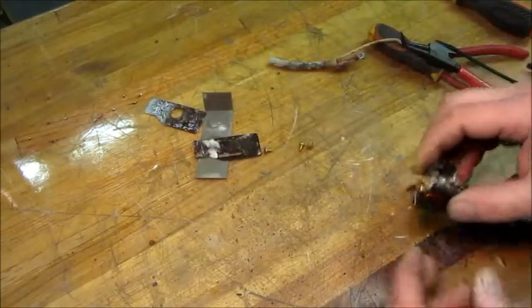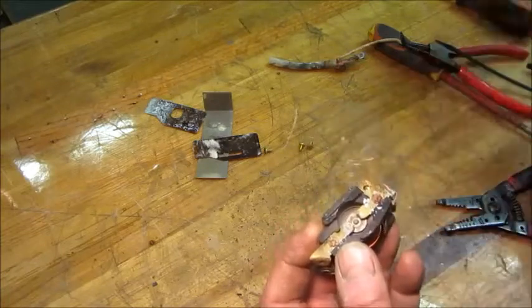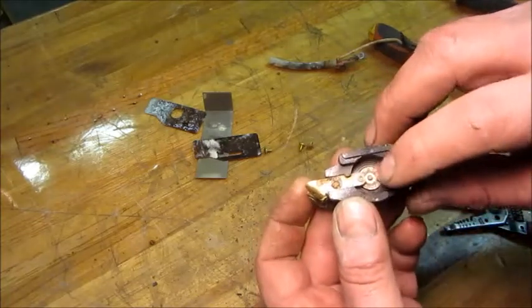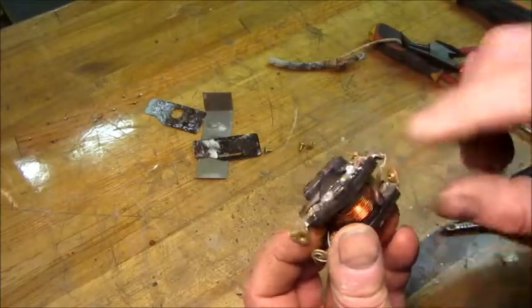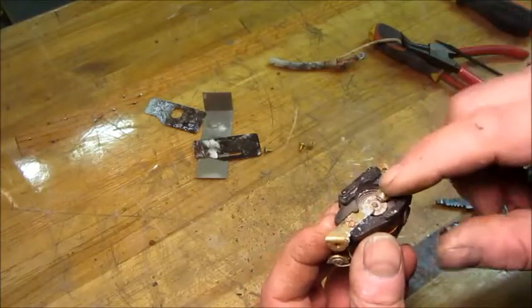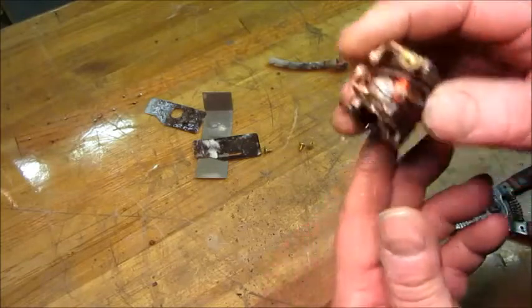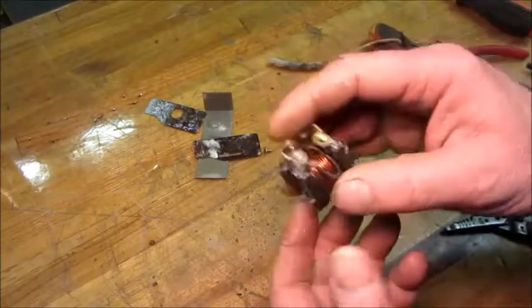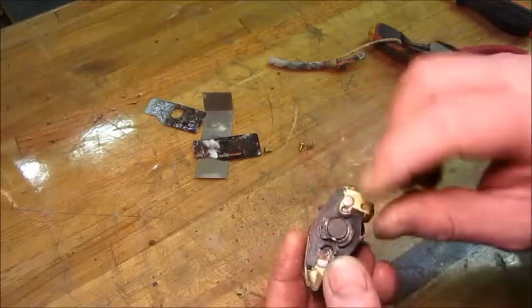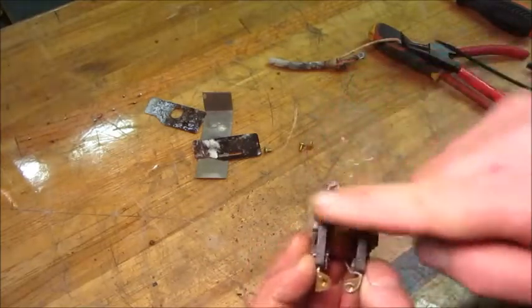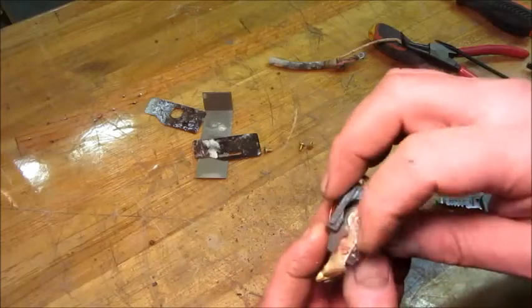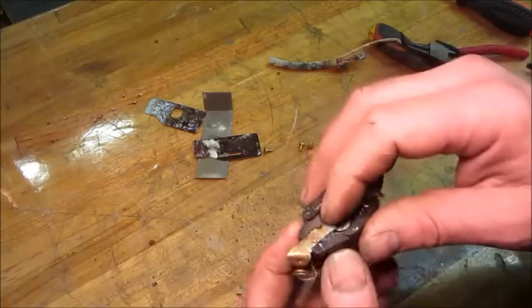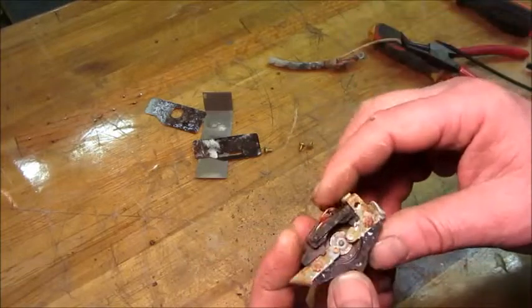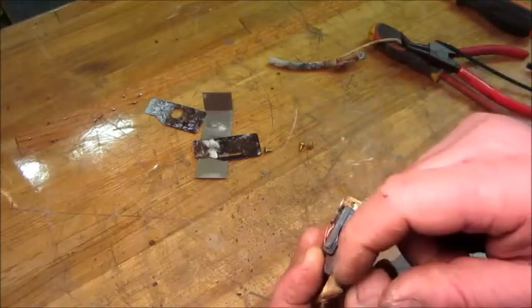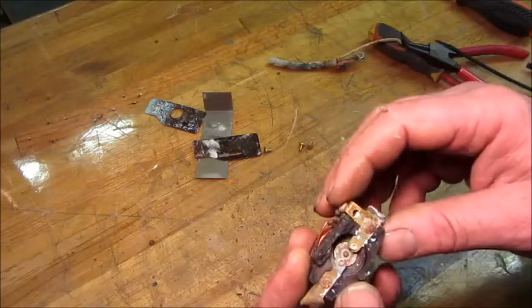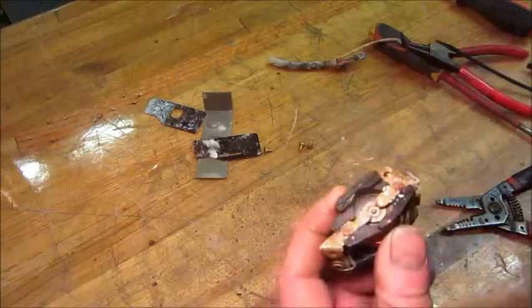You'll probably hear the ultrasonic going in the background. So that little disc in there is pulled up magnetically by this coil during starting, and it bridges these 2 points together to actuate the start winding. But it's gone totally solid. The last one of these like this, I had to drill a little hole in the center of that and drive it out with a punch and hammer. But the first thing to do is to take these 2 rivets out and get the contacts out of the way so that thing can actually come out of there. So I'm going to use the Dremel and a little cutting wheel and grind the heads off of them to start the repair process for this.